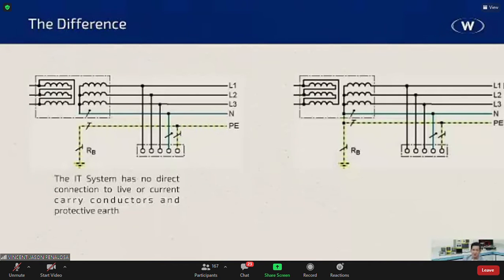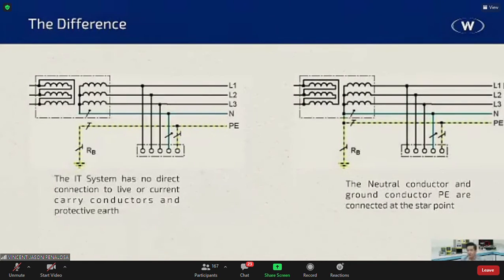If you said that one, then you are correct. That would be the IT system. Now, both of them are on a Y secondary, right? Now, commonly we know the ungrounded system usually as a delta system where the ground is floating. But in this case, you're going to be on a standard 5-wire system where you have line 1, line 2, line 3, and neutral, and there is no direct connection between live or current carrying parts.